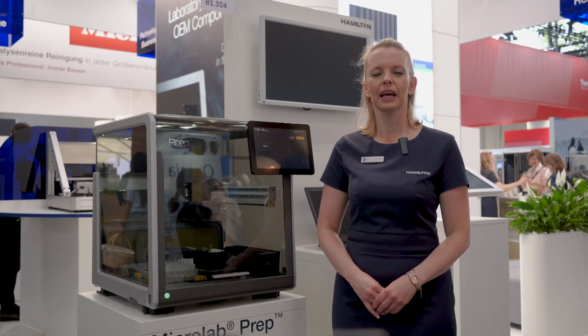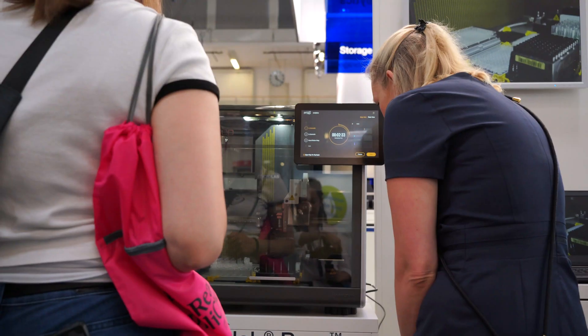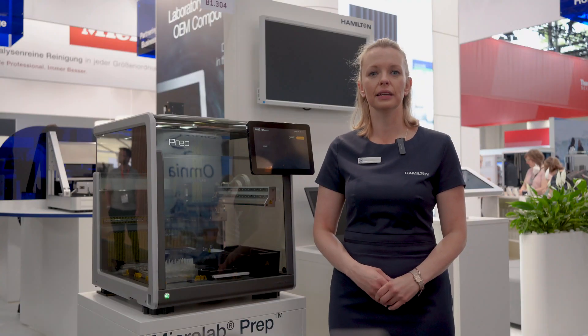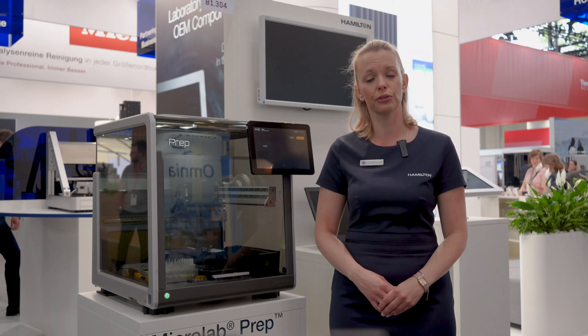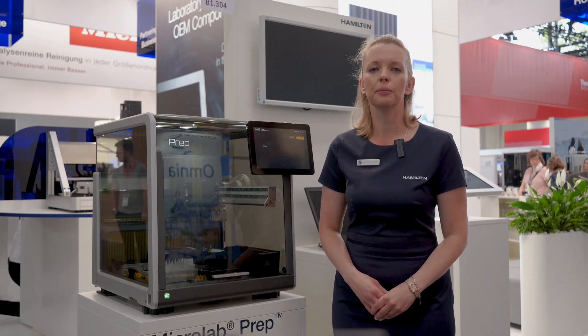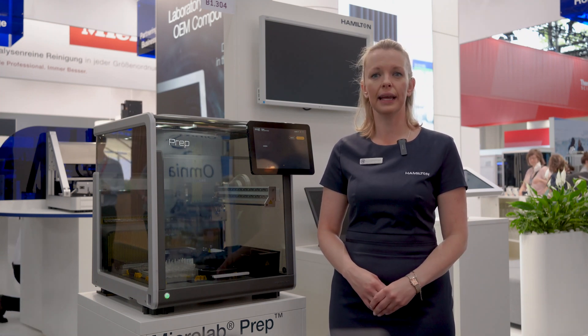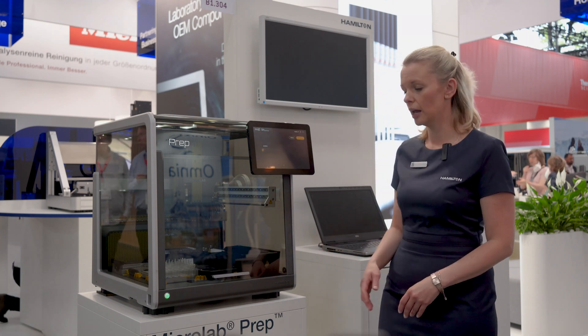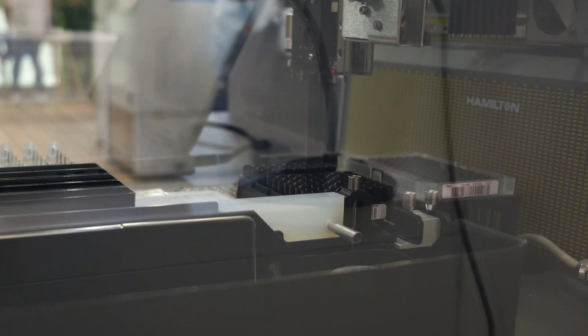Hello, my name is Sylvia Hofmann-Simon. I am an Inside Sales Specialist at Hamilton Robotics and we are here at Hamilton's booth at Analytica 2022. I want to show our entry-level liquid handling system, the MLPREP — a compact, affordable and user-friendly instrument. The MLPREP is 112 x 80 x 90 cm in size and fits easily on a laboratory bench.